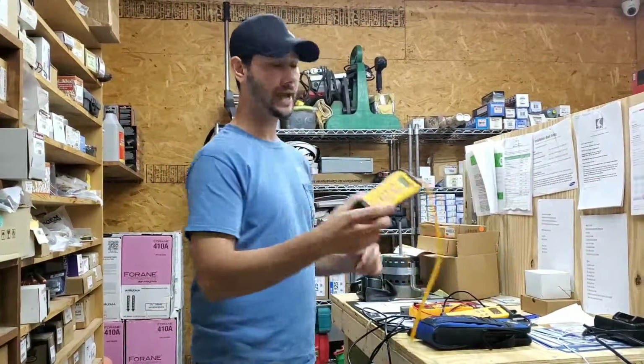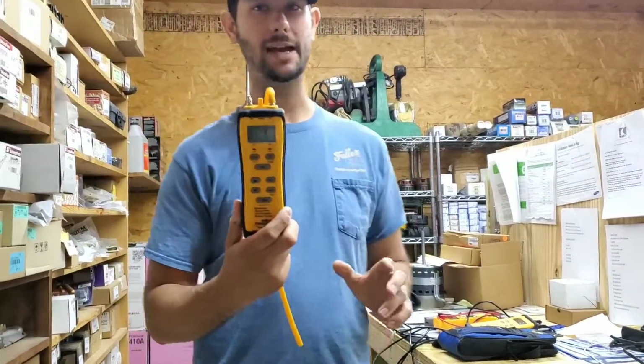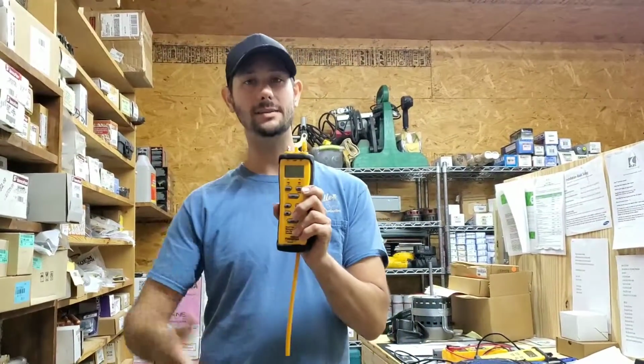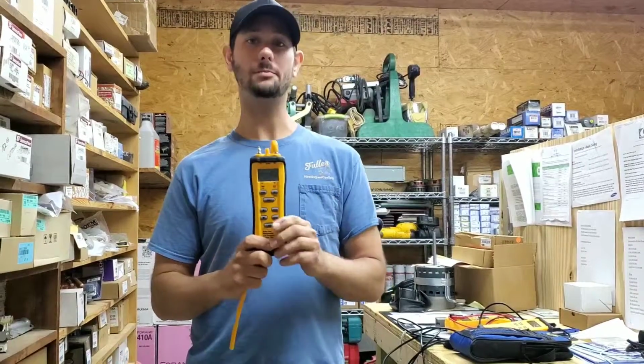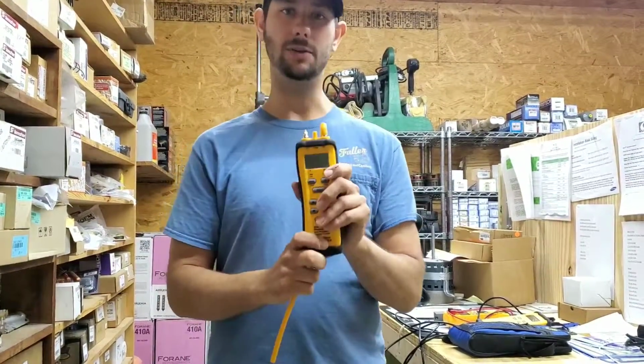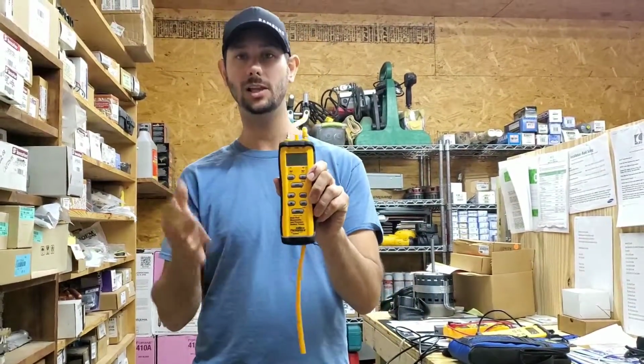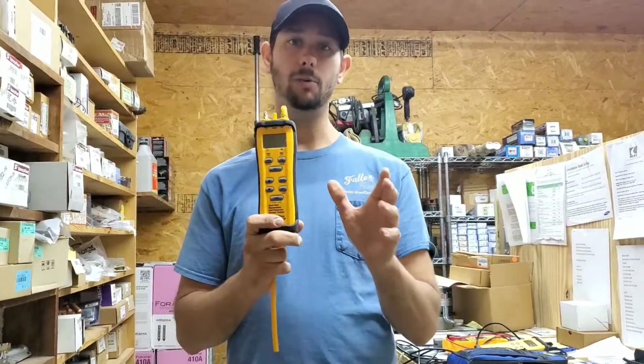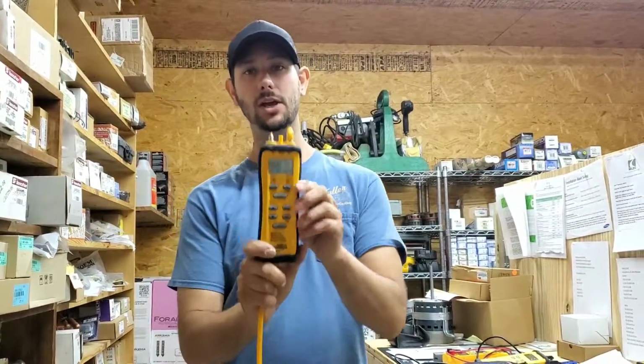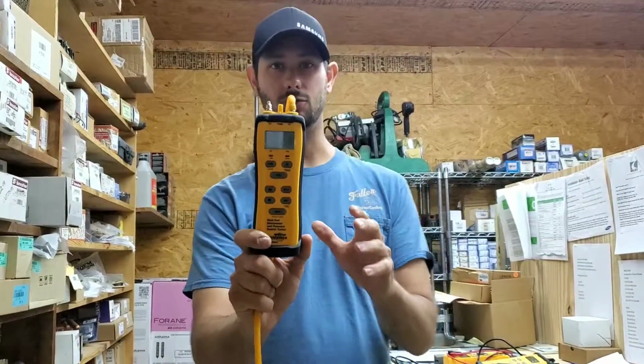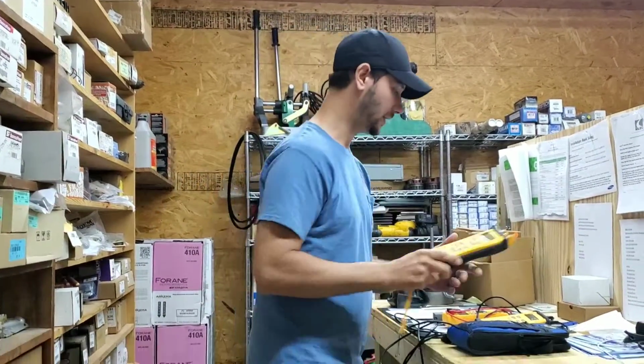So the first tool we have is a manometer, used to check gas pressure and make the measurements and then make the adjustments that you need. When you install a new unit in the field, it doesn't come preset. You have to adjust it. For natural gas, 3.5 inches of water column is the go-to. For propane, it's around 10 inches water column. You need this to be able to make that measurement. So a manometer is the first tool that I recommend.